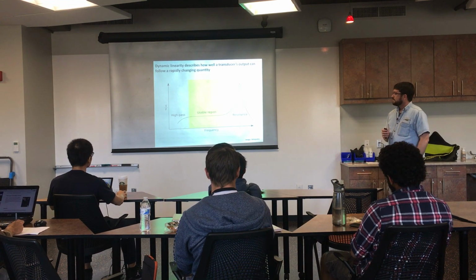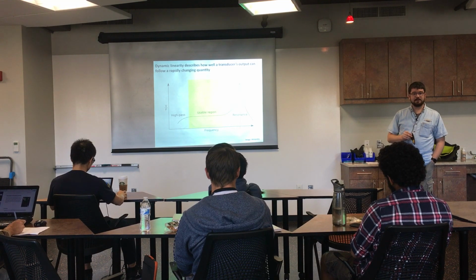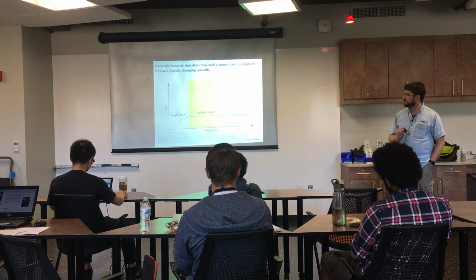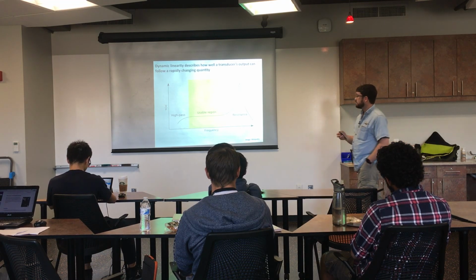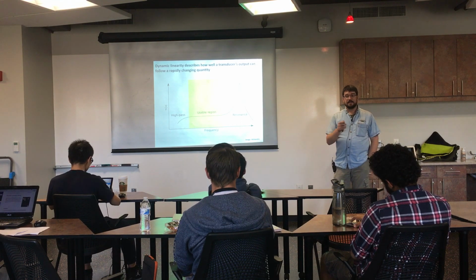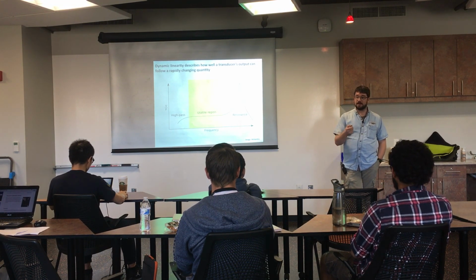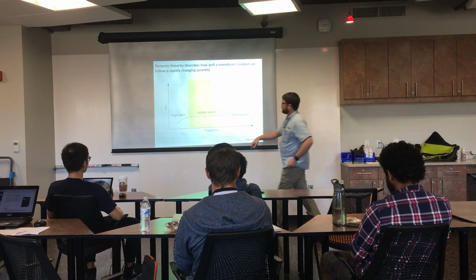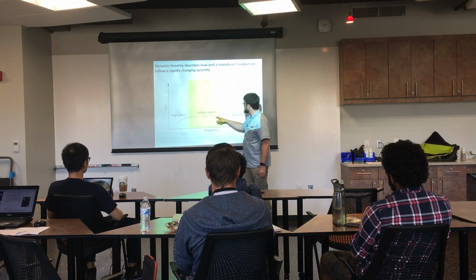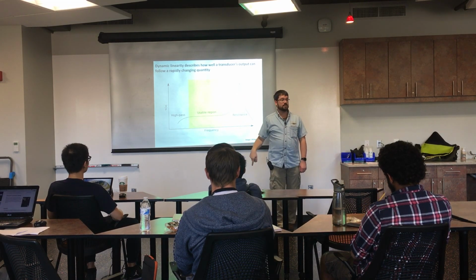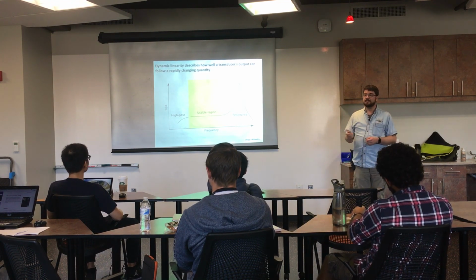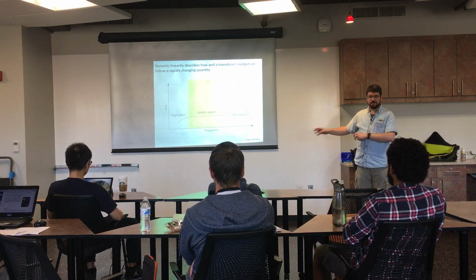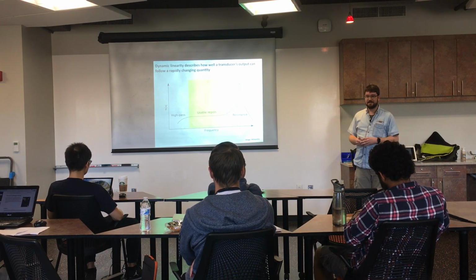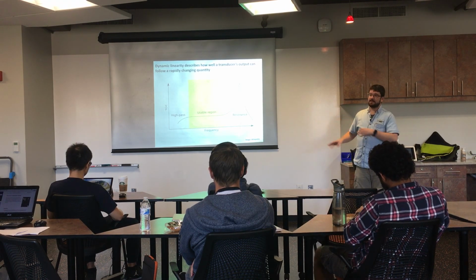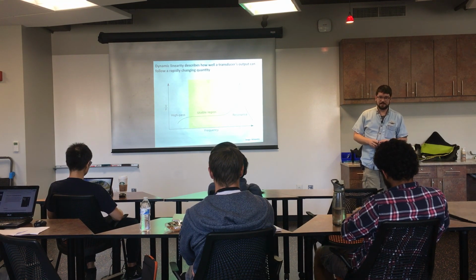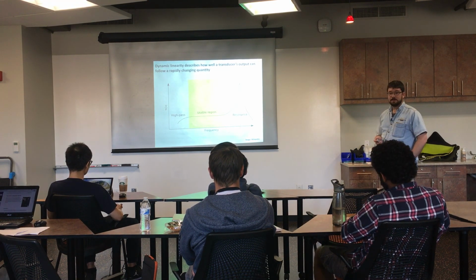Another thing considered less than it probably should be is the dynamic linearity of the sensor - essentially the transfer function of the sensor, how its response changes as a function of frequency. A DCDT, for instance, has a limit to how fast it can respond, which relates back to response time. You get some funky transfer function where at very low frequencies you might see a high-pass effect, then a usable region, and out further the sensor might hit some kind of resonance. That data wouldn't be valid unless you account for this. This is tricky to pin manufacturers down on, since often they haven't done this test for various sensors - try finding a dynamic linearity curve for a load cell, it pretty much doesn't exist. So you might have to do that yourself or beg them to do one for you.